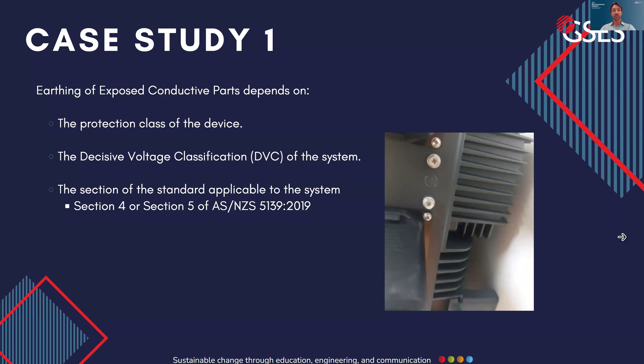The protection class, DVC, and configuration of the system matters to how the earthing of exposed conductive metal parts is done. However, generally speaking, the external earth lugs provided by the OEM should be used. We're showing a picture of what those external earthing lugs look like. Earthing of exposed conductive metal parts is discussed throughout AS3000, and most OEM installation guides call out how and when to use these earthing systems. Thankfully, this is quite an easy and inexpensive fix, but it's actually very important that this is done correctly going forward.